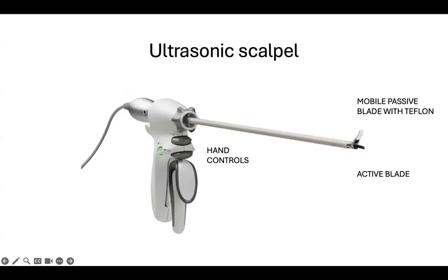This harmonic probe has the handpiece connected at the back. So this is where the conversion of electrical energy to sound energy happens. This sound energy, or the vibration, is directly transmitted to this instrument. And here, if you see, there are two blades for this instrument. The one with the white coating, or the Teflon coating, is the passive blade, and that is the only blade which moves. That's why I've written mobile passive blade.